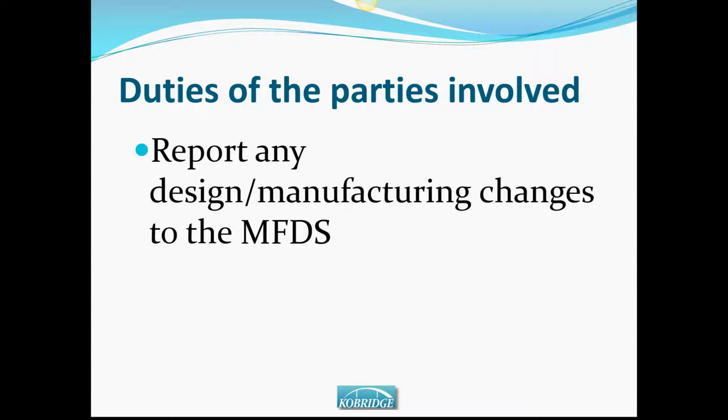Another thing to consider, speaking about the duties, is for the license holder to report any design or manufacturing change to the MFDS, the Ministry of Food and Drug Safety, like the Ministry of Health. So whenever such changes are communicated from the manufacturer, then they must be evaluated based on their impact and then communicated to the MFDS.